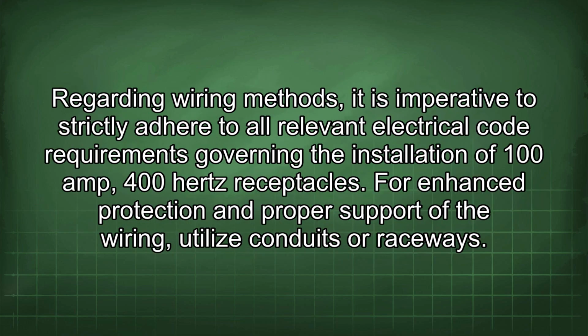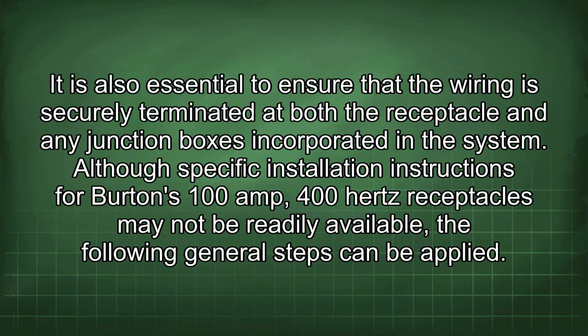Regarding wiring methods, it is imperative to strictly adhere to all relevant electrical code requirements governing the installation of 100 amp 400 Hz receptacles. For enhanced protection and proper support of the wiring, utilize conduits or raceways. It is also essential to ensure that the wiring is securely terminated at both the receptacle and any junction boxes incorporated in the system. Although specific installation instructions for Burton's 100 amp 400 Hz receptacles may not be readily available, the following general steps can be applied.